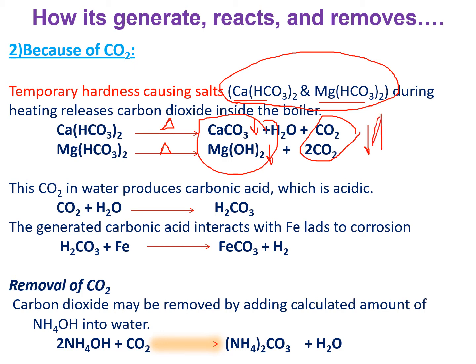The CO2 gas present in the boiler interacts with water and produces carbonic acid. This carbonic acid interacts with the iron and produces iron carbonate. Iron goes from metallic iron (zero state) to ionic iron (Fe2+) — this is corrosion. Iron is involved in corrosion by releasing hydrogen gas. From the electrochemical series, iron is an anodic material; it interacts with acids and produces hydrogen gas.